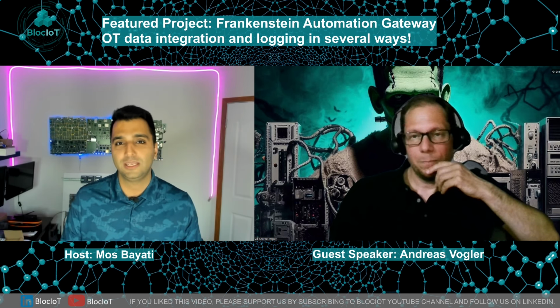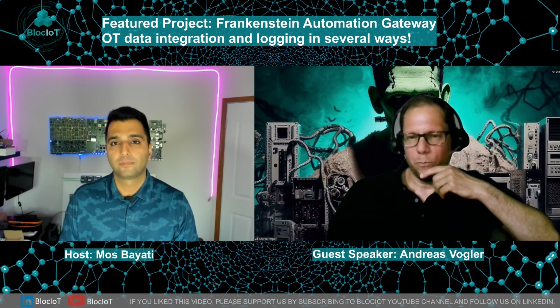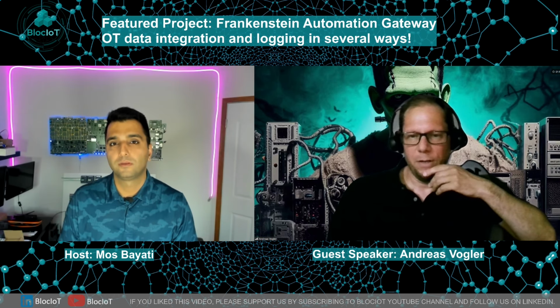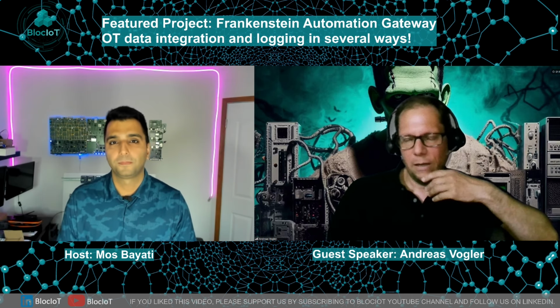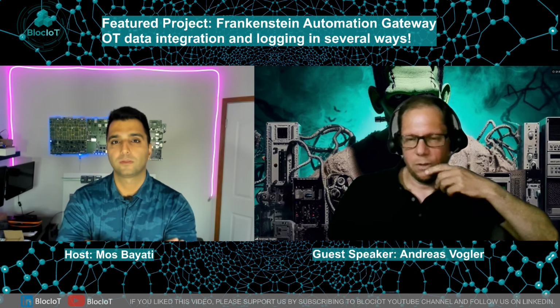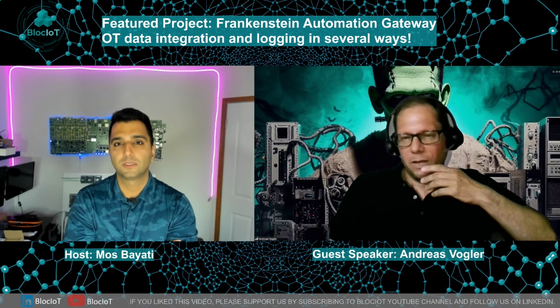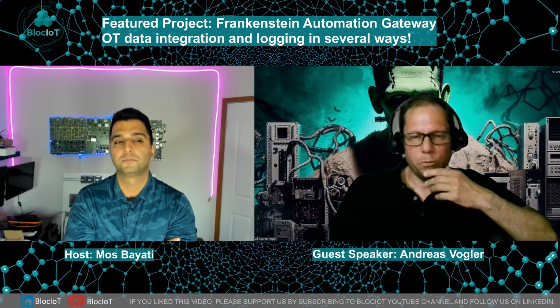Personally, I think OPC UA is a very great standard, but the implementation can be hard because, again, it's very comprehensive. That is maybe one of the problems of OPC UA. You can certify OPC UA servers, no problem at all, but that does not necessarily mean that it provides all the functionality of all the specs which are available. Then you have clients which are not capable of some functionality, and then you don't have this compatibility. On the other hand, it is good that there are a lot of different things available, so you can find the one that you need for your use case.